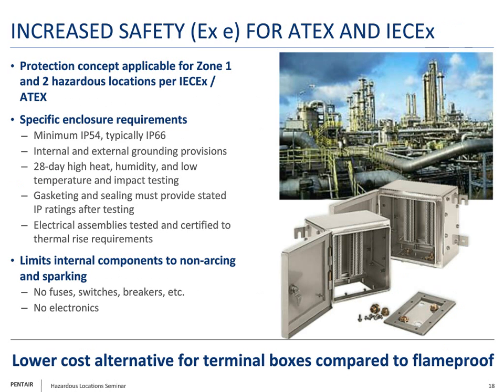Okay, so we're moving on to another protection concept called increased safety, and this is for ATEX and IECEx standards. It's applicable in Zone 1 and Zone 2. What makes these enclosures and systems a little unique is at a bare minimum they've got to be IP54, but typically you see IP66 performance. They have internal grounding and bonding provisions, and they have been tested extensively.